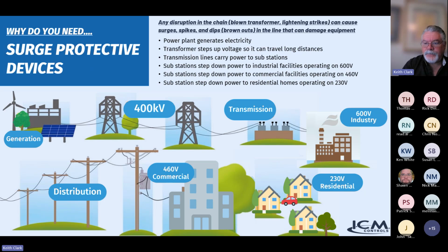Then it comes into a substation where it's transmitted downstream to industry. First, we've got industry in big industrial complexes, which typically run on 600 volts. Then it'll go through another substation, which steps it down from there to send 460 to our commercial facilities. So any commercial type applications that our HVAC people are working on typically will fall in that 208, 230, 460, a lot of times three-phase power.